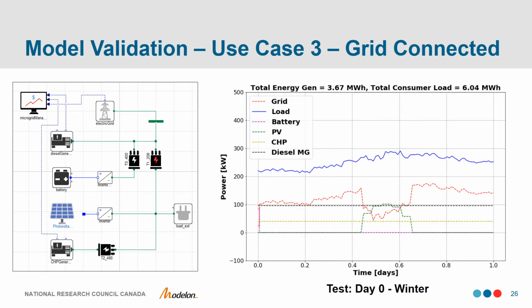Looking at the chart on the right, you can see an immediate difference in how the system operates with the addition of the electric grid. One of the most important things to notice is that the diesel generator is now operating continuously at its minimum loading value of 96 kilowatts. CHP continues to operate at 40 kilowatts, and any remaining demand is satisfied through power supplied by the grid.